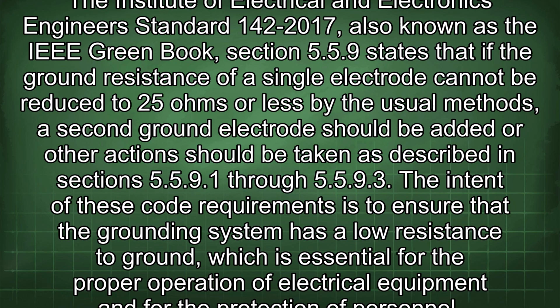The Institute of Electrical and Electronics Engineers Standard 142-2017, also known as the IEEE Green Book, Section 5.5.9 states that if the ground resistance of a single electrode cannot be reduced to 25 ohms or less by the usual method, a second ground electrode should be added or other action should be taken as described in Sections 5.5.9.1 through 5.5.9.3.